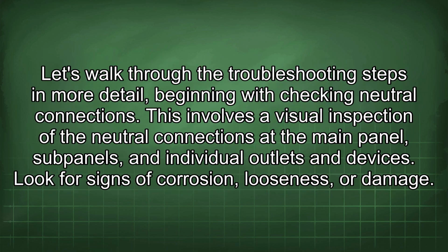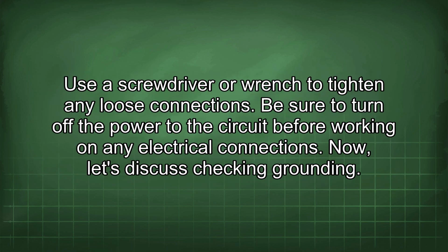Let's walk through the troubleshooting steps in more detail, beginning with checking neutral connections. This involves a visual inspection of the neutral connections at the main panel, subpanels, and individual outlets and devices. Look for signs of corrosion, looseness, or damage. Use a screwdriver or wrench to tighten any loose connections. Be sure to turn off the power to the circuit before working on any electrical connections.